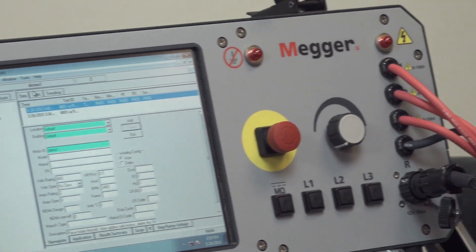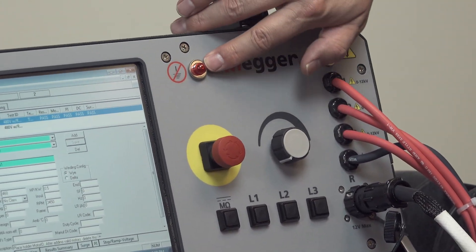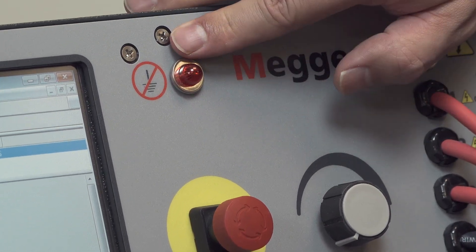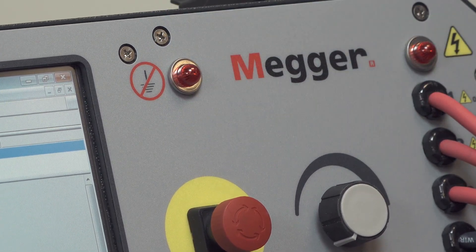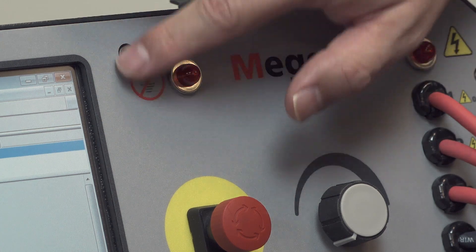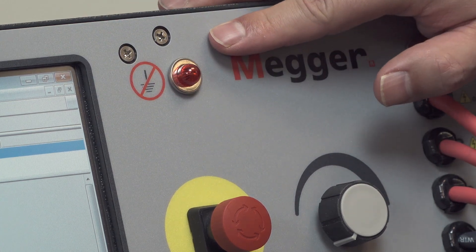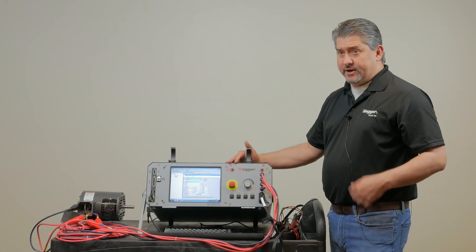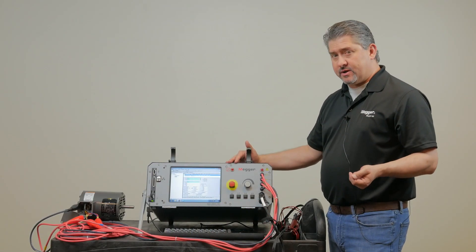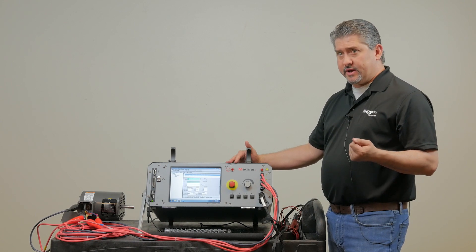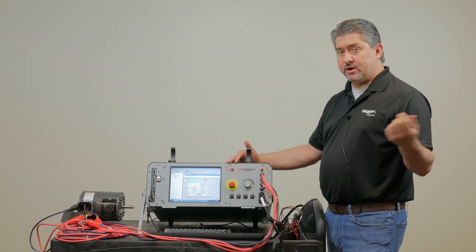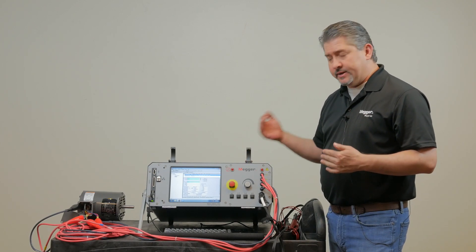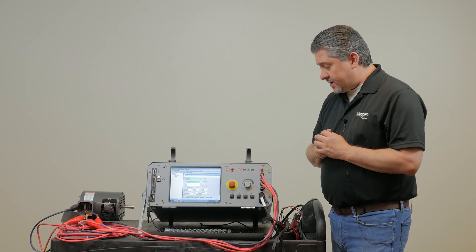Then on the right side we have the open ground indicating light. This would illuminate if your power supply was not properly grounded. This is also associated with a safety interlock that wouldn't allow the high voltage power supply to be energized if you didn't have a proper ground. Now, this can be overridden if you're in a situation where you're connected to an ungrounded distribution system, but proper safety precautions need to be taken prior to overriding that interlock.